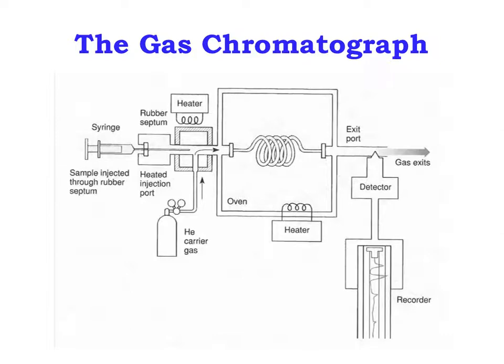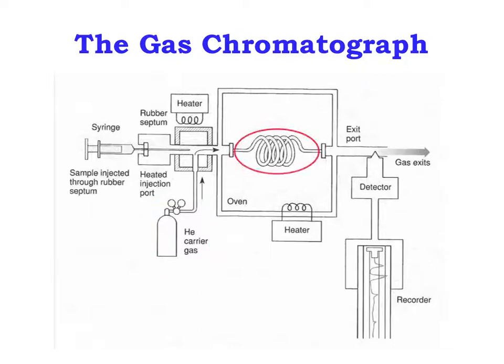An integral part of the instrument is the carrier gas, which is typically helium, nitrogen, or argon. Do you remember its purpose? If not, back up and review the earlier slides. Once vaporized, the sample enters the heated column, where the components in the sample equilibrate between the liquid and vapor phases.